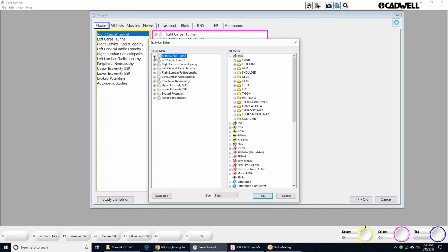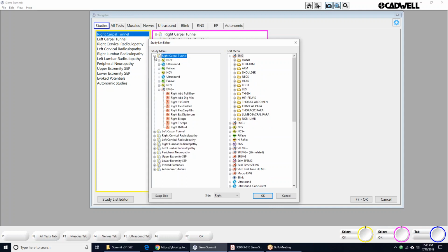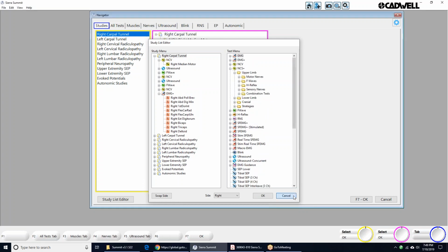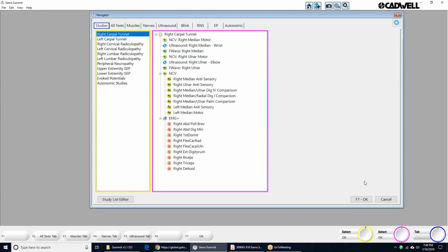If the customer is going to start using NCS Plus, you'll also want to create studies. You'll want to probably delete out the NCV tests out of their studies and add tests from the NCS Plus menu. Okay, so those are all some special things you'll need to do if you're doing an upgrade.